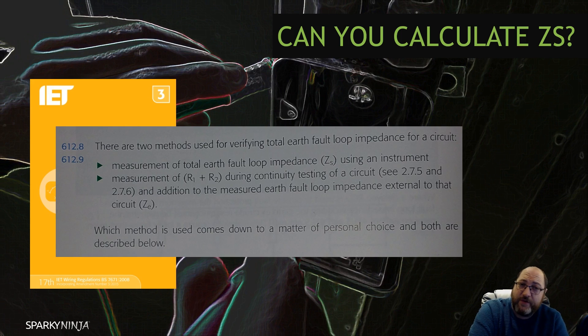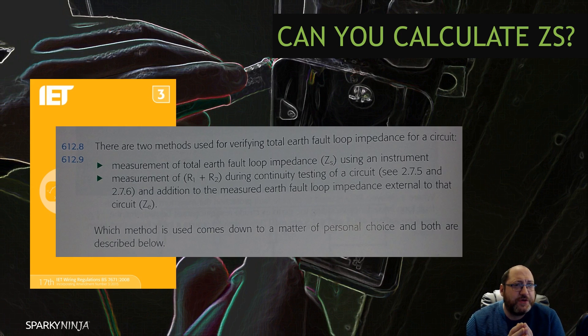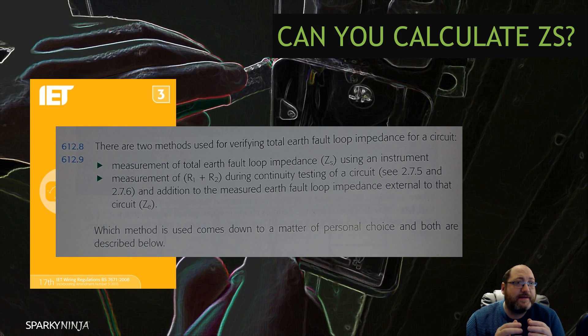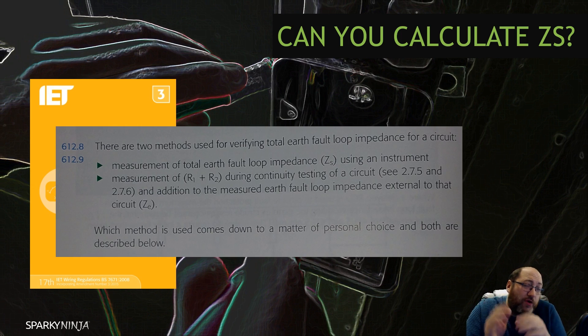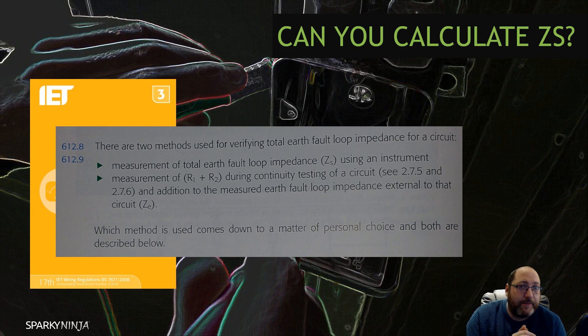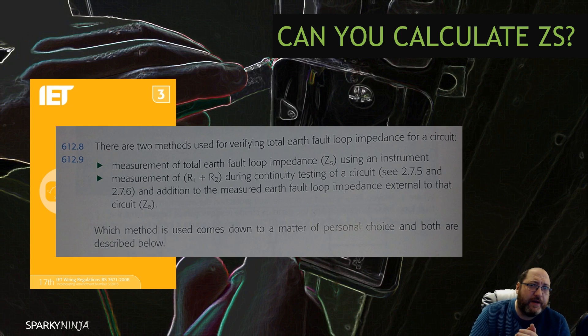But this sentence I just don't like at all. It says which method is used comes down to a matter of personal choice, and both are described below. I don't know why they said 'personal choice' — according to the wiring regulations, you measure, and then you calculate to verify a poor measurement. Personal choice is bad wording — very bad wording — because we're going to end up with what we have now: people just calculating it because it's quicker, cheaper, and they just can't be bothered.